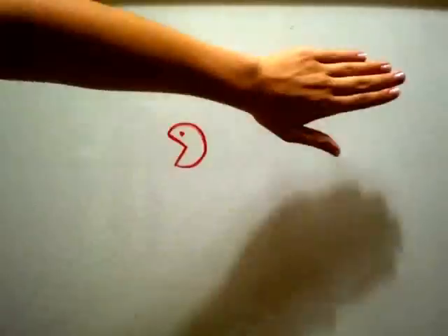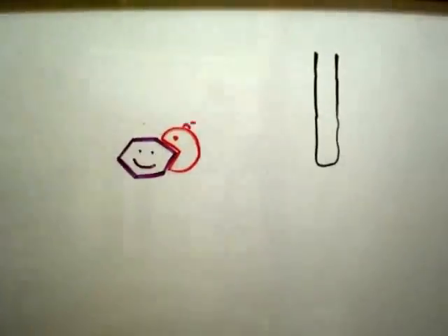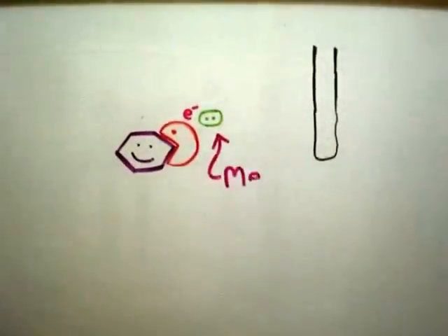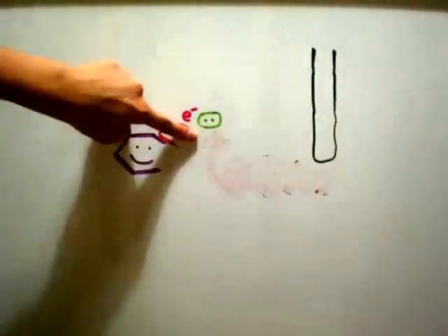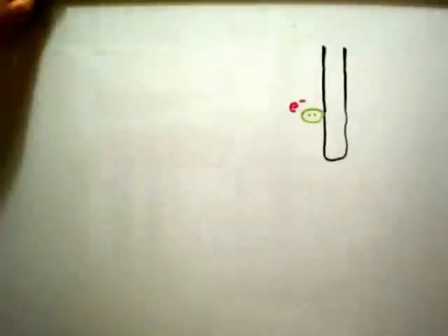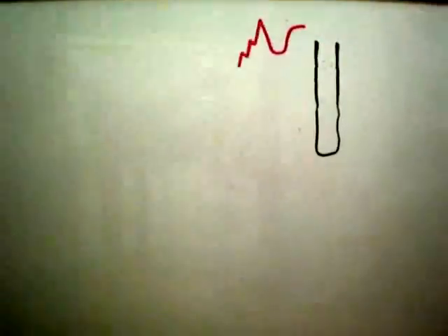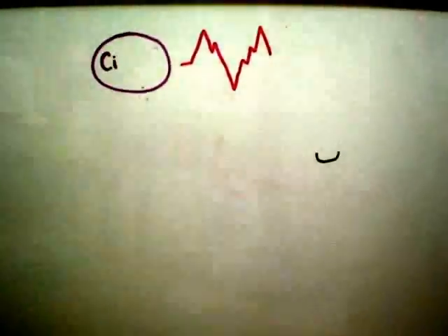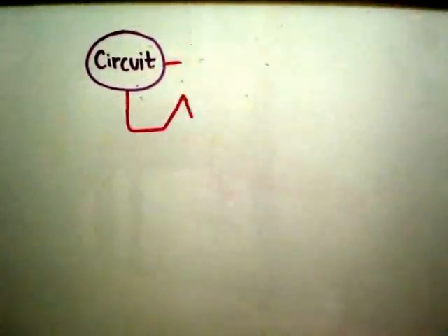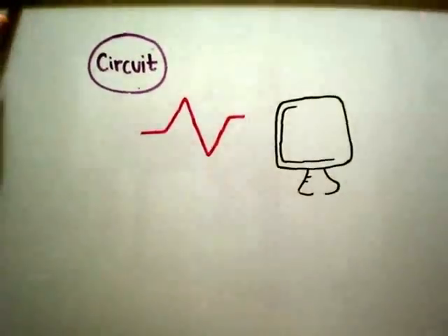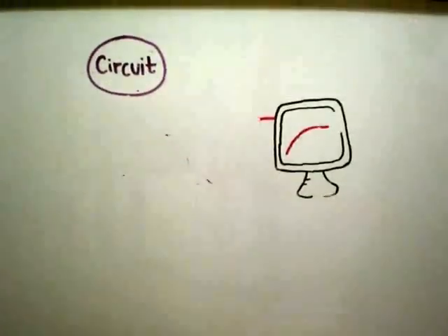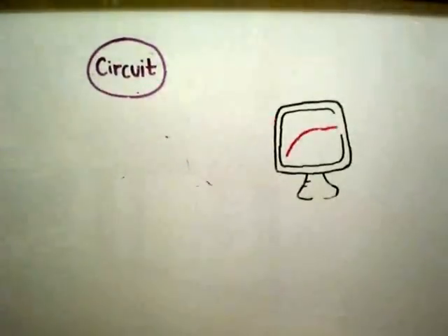Once we produce electrons, we need to shuttle them from the enzyme to the probe. Small units called electron mediators that temporarily hold electrons pick up the electron from the enzyme and pass it to the transducer. This conductive transducer then sends the electrons to signal processing circuitry that amplifies and reduces the noise of a signal, making it easier to use. The computer now acquires the signal and with some fancy calibration equation turns electrical data into concentration data.